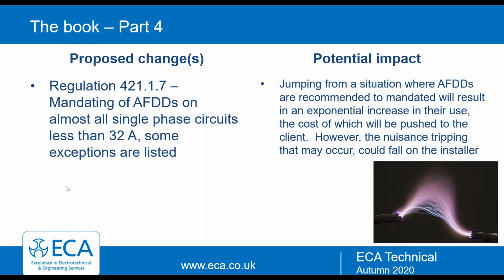Yeah. Just a couple of questions that have come in. Sorry, this is going to backtrack again on a few bits here. A few questions about socket outlets. What if the socket were like the average 3-pin? I'm guessing that's in relation to the RCD and omission. I don't think the proposed change specifies. It doesn't. It says all sockets rated up to 32 amps need to be RCD protected. So it doesn't make the distinction between BS 1363s or 60309 or commando style type plugs either.